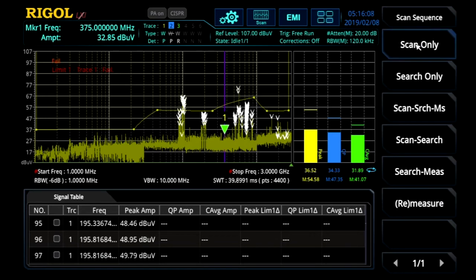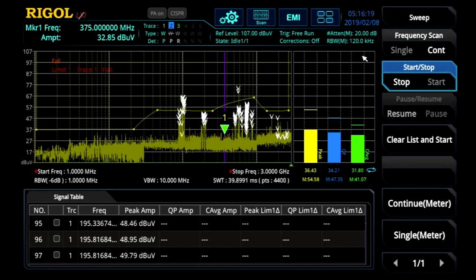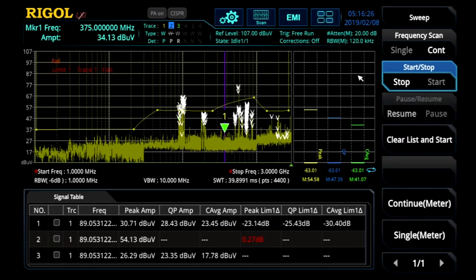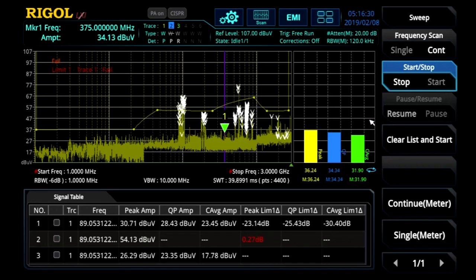The scan sequence is the critical operation area. You can do scans, search for signals in the signal table, do measurements, or do all of them together. Here we're going to do a little bit of everything. To start, we go to the sweep menu. When I hit start, it scans, looks at peaks against those limit lines and against the peak detector areas. We've highlighted a key area at about 375 megahertz, which we know is a harmonic coming off of our test device, and we're able to do real-time measurements on multiple detectors at that exact frequency. All combined — scans, signal tables, measurements — as well as the ability to save and archive data, setups, and test reports, really makes the EMI measurement application a complete solution for pre-compliance testing with a real-time spectrum analyzer from Rigol.